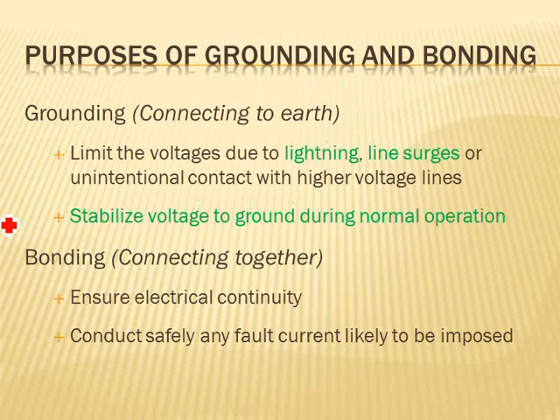Transient voltages on an ungrounded system are very destructive, and on a grounded system they are less destructive. That's the advantage with line surges too. Utilities take a 138,000 volt transmission line, switch you to another transmission line, and create that transient into your system. If your system is grounded, its ability to absorb the transient is much higher than if it's not grounded.